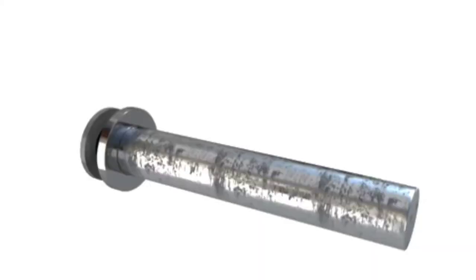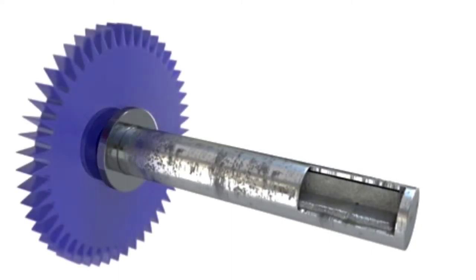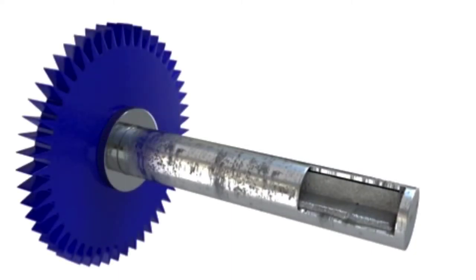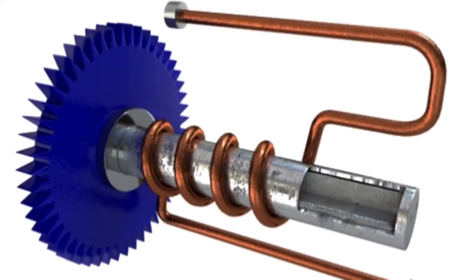In a melting alloy overload relay, the eutectic alloy is housed in a tube along with an inner shaft cemented in place. This tube is connected to a ratchet wheel. The temperature of the alloy is controlled by a heater coil wrapped around the outside of the tube.